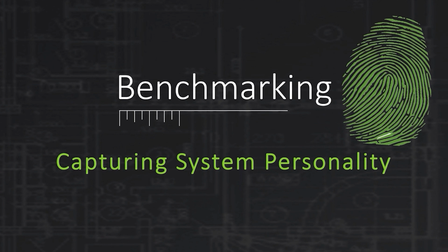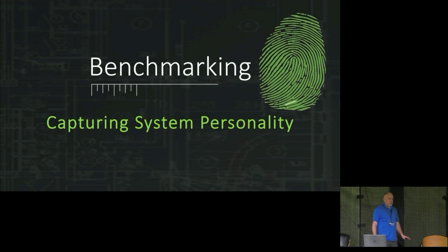Now this is probably my biggest pet peeve right now. I see a lot of reports come in where somebody didn't benchmark the system. And this benchmarking is capturing our personality. So after we commission a system, you want to be able to send a tech out who's got a lower skill level than you and have them hook up MeasureQuick, and MeasureQuick will tell them if everything's in the correct target ranges and how that system's supposed to operate. And that's what benchmarking the system is all about.